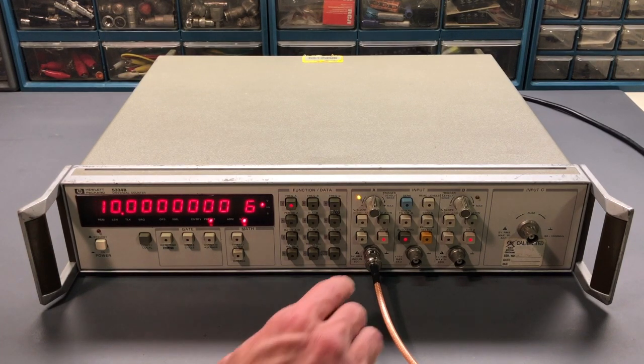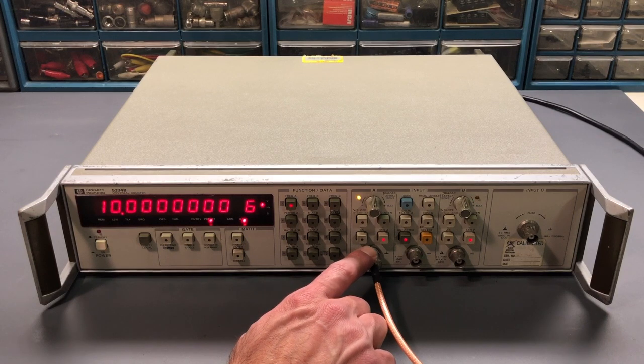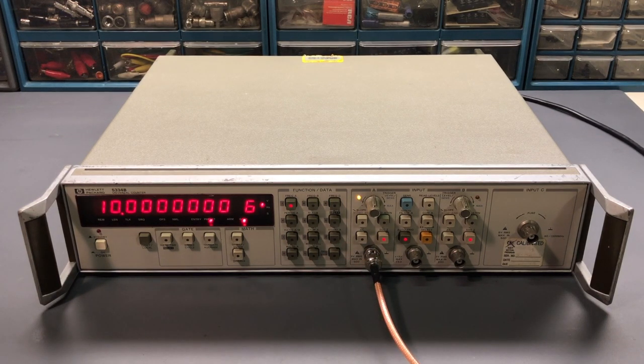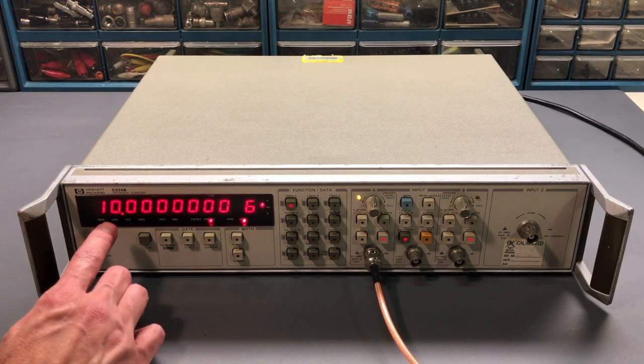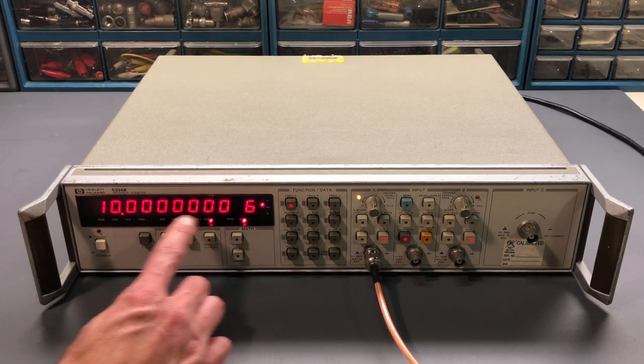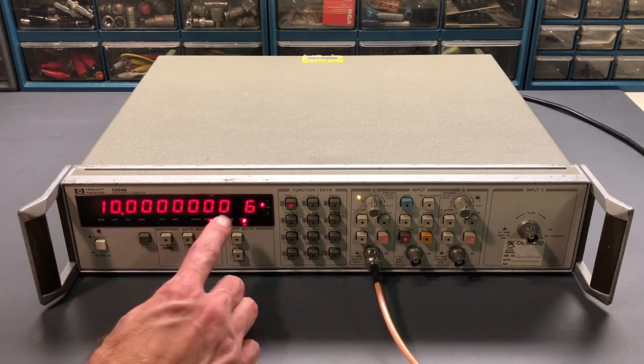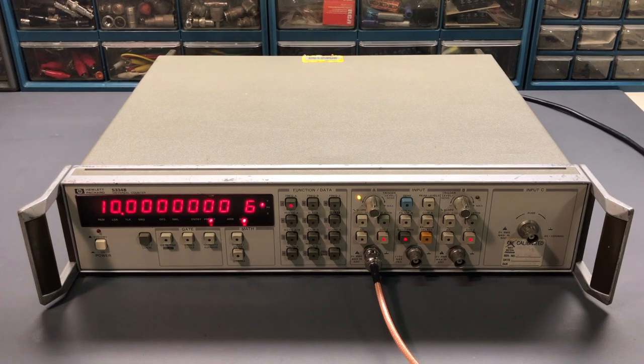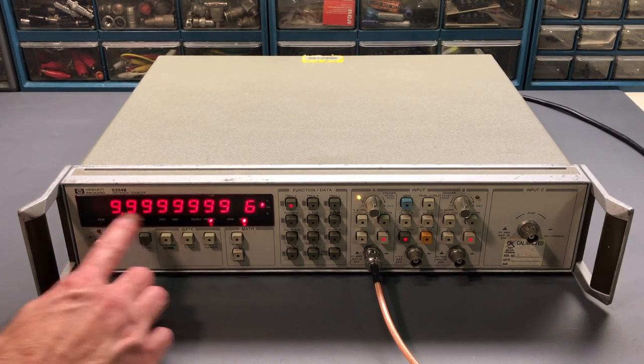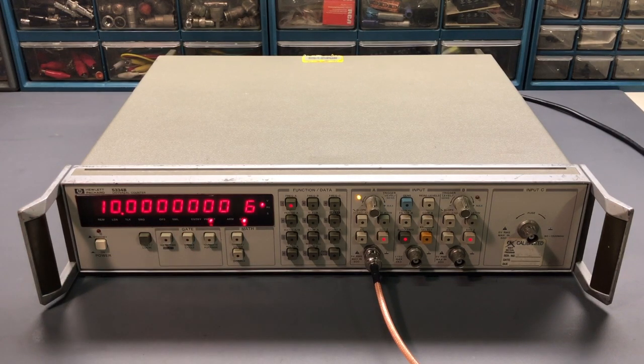Right now, the signal that's coming into channel A is from the external reference oscillator, that GPS synchronized oscillator that I previously used. And it's sitting precisely at 10 megahertz. So you can see over here, we do have an indication of 10 megahertz. Now it sometimes will toggle down to all nines, perfectly normal. When it's sitting right at a specific frequency, sometimes it'll do like we see here. Again, perfectly normal that it will toggle between the 9 and then the 10.